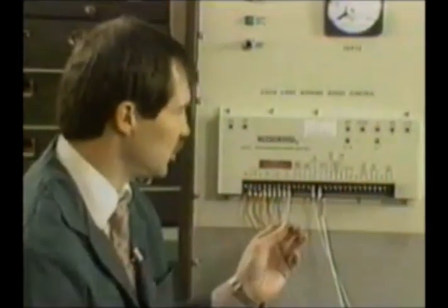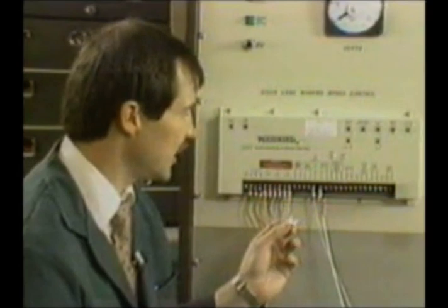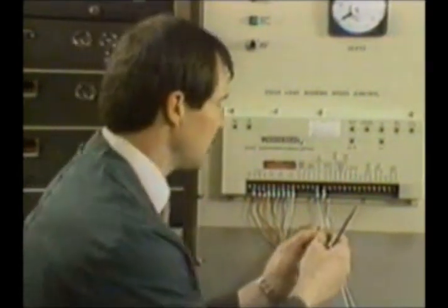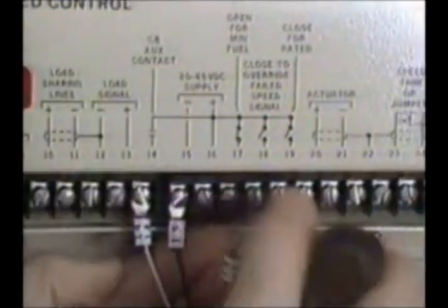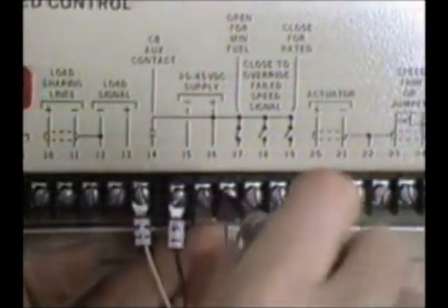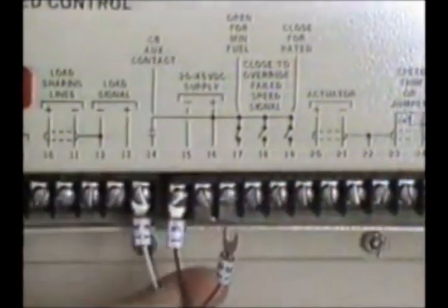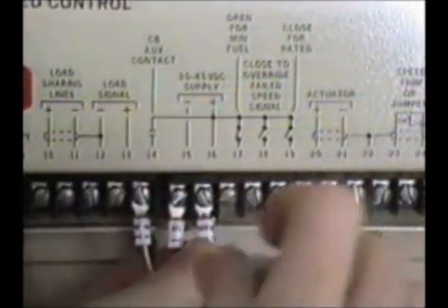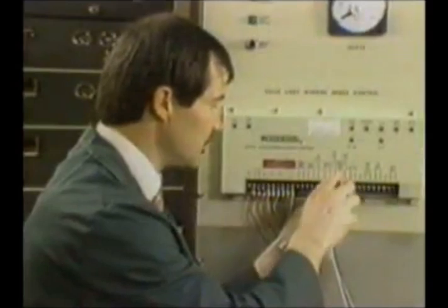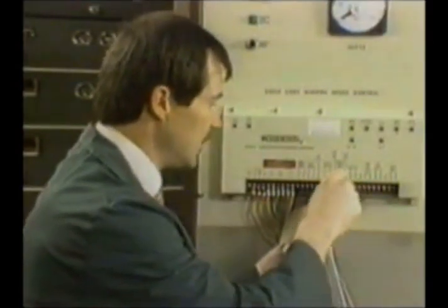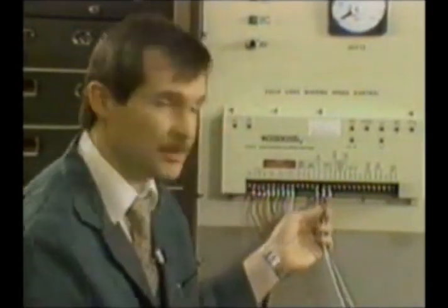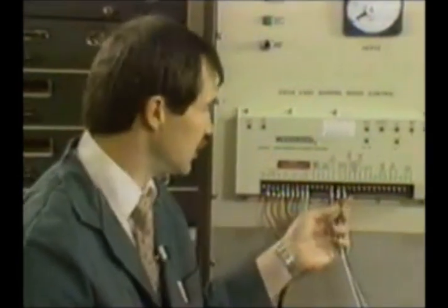So what I'm going to do, I'm going to use this little jumper here. I'm going to jumper terminal 16 and terminal 17 together so that terminal 17 is always high and will not come into play today in this demonstration. If you don't have anything on terminal 17, you will not be able to start your prime mover. So if you don't have terminal 17 jumpered to 16, make sure you have it going to some contact that will provide an input voltage to it so you can start the engine.